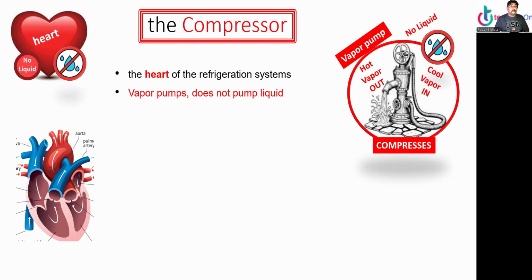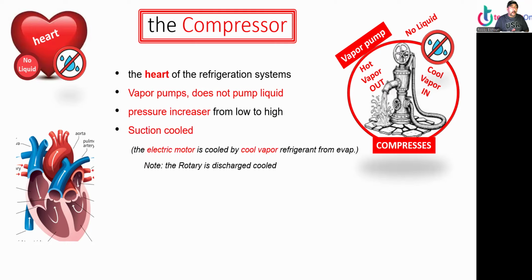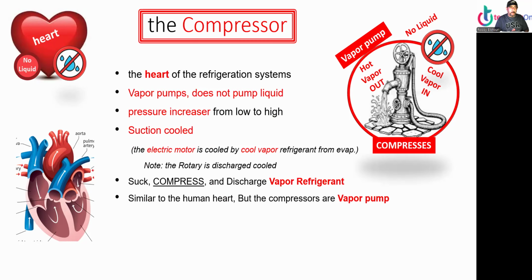The compressor is the heart of the system, ready? It's a vapor pump, it does not pump liquid. People think the pump is a liquid vapor pump. It's a pressure increaser from low to high. And it's suction cooled, cooled by the suction line, except the rotary is discharge cooled. The compressor has one main job, which is to suck, compress, and discharge vapor refrigerant. Similar to the human heart, but the compressor is a vapor pump.